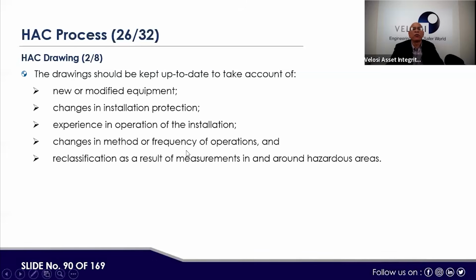The drawing should be kept up to date. One thing is whether it's an as-built drawing. Sometimes the plant has been modified and you are making the HAC drawing on the old version. And sometimes you have made the older HAC drawing, and then the plant has been modified, and you have to update the HAC drawing as per the newly installed equipment. So what do we need to take care of?